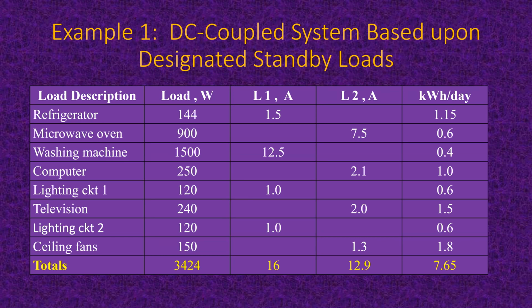Look at your yellow sticker and estimate your annual kilowatt hour consumption, divide it by 12, divide it by 365 or whatever to get your daily kilowatt hours, and figure out how many watts it takes to get that many kilowatt hours when the thing probably has about a 50% duty cycle at most. And 144 watts is pretty typical for a 21 cubic foot refrigerator. So that's about 1.5 amps, and this is going to be on a 120/240 connection. So we'll put that on L1.